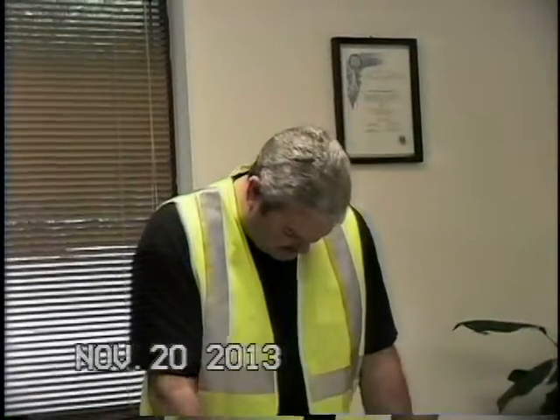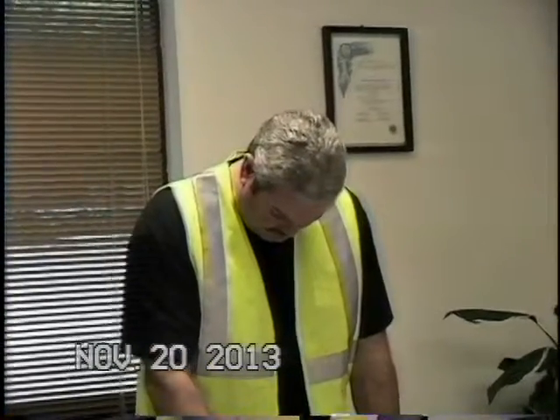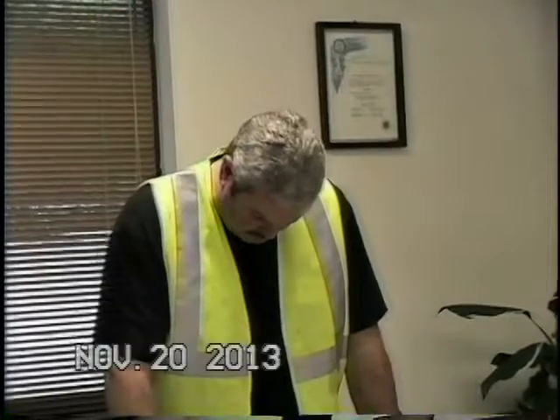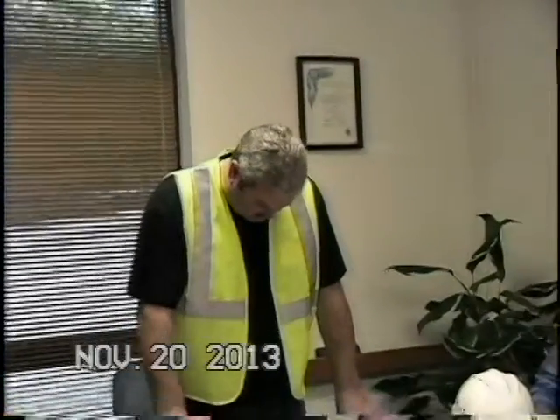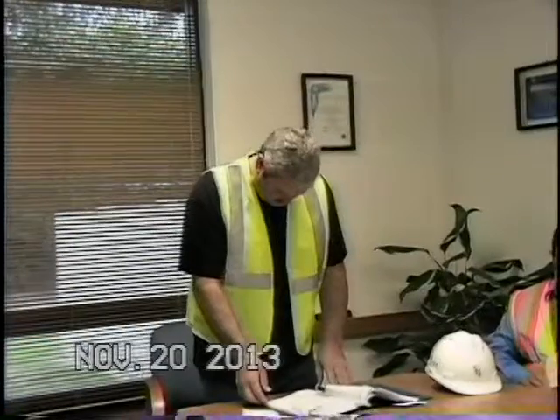Okay. So on here, the daily maintenance, and basically I'm just going to read it off of here. Observe the operating temperature and general conditions. That's just make sure it's up to temp, make sure there's no issues. Make sure that the flow of combustion and ventilation air to the boiler is not obstructed. And this is a very smart boiler. Just do a visual, but it will let you know if there's a problem. And a little bit later on, we'll go into all the error codes.